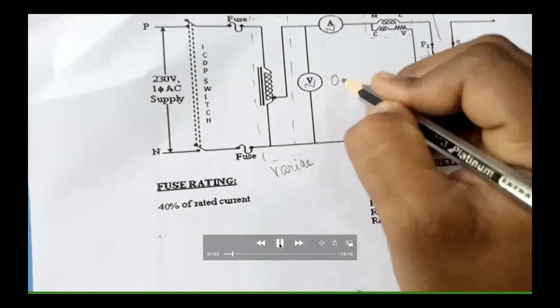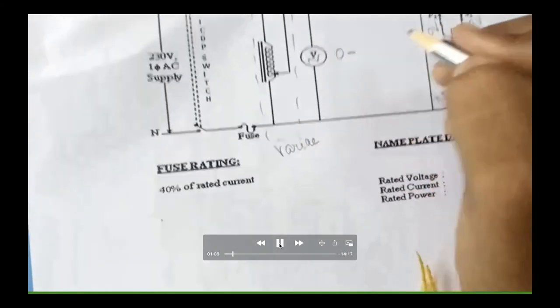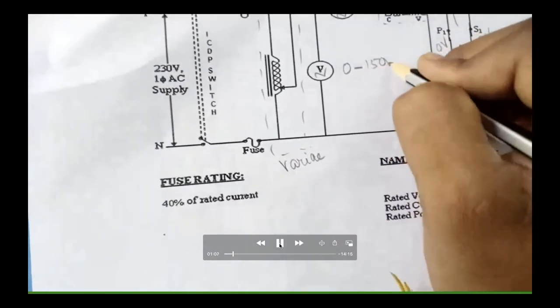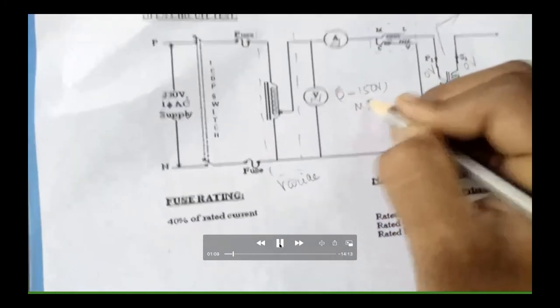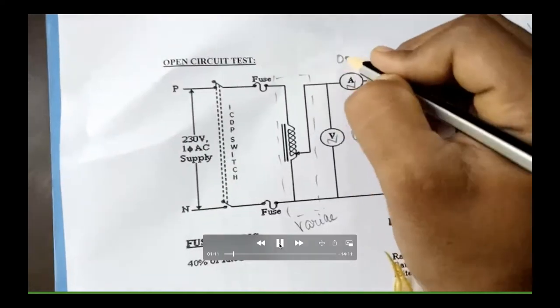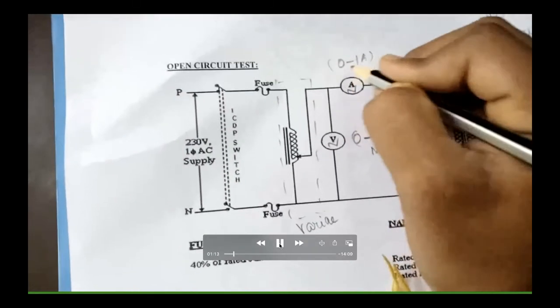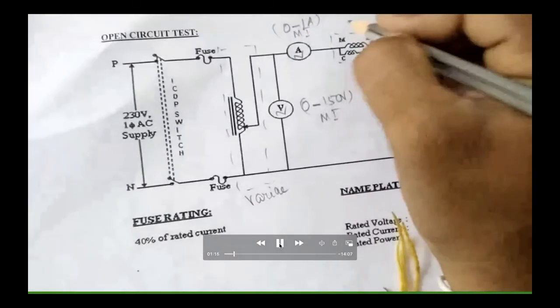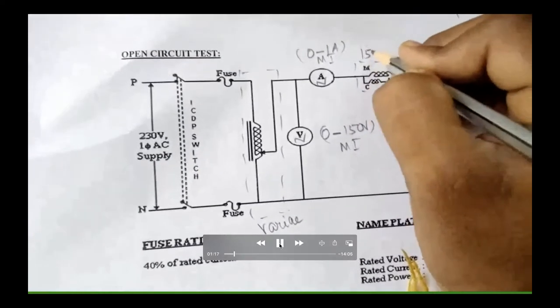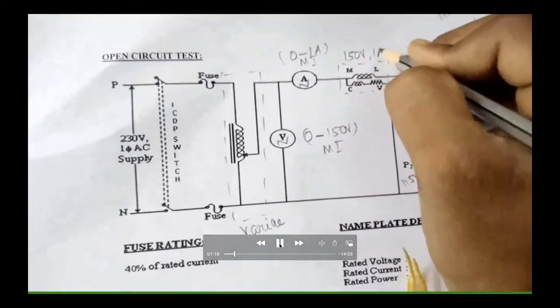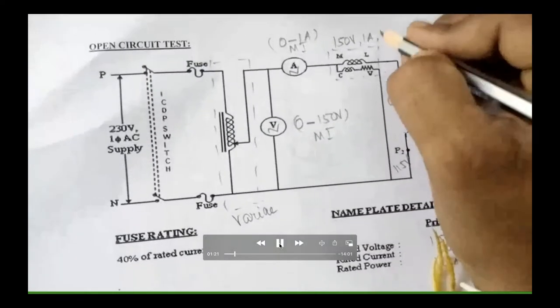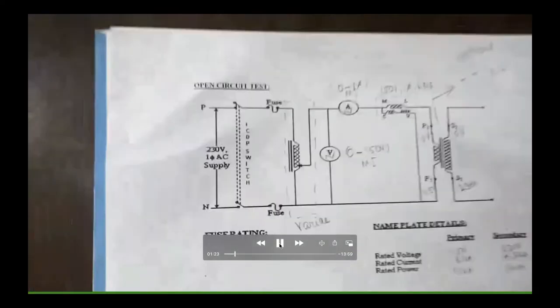Since the primary voltage is 115, we can give 150 volts on the moving iron voltmeter, and the primary current will be 0 to 1 amp because it is open circuit. So the current will be minimum, and 1 amp is sufficient. So 150 volt per 1 amp, low power factor, LPF.